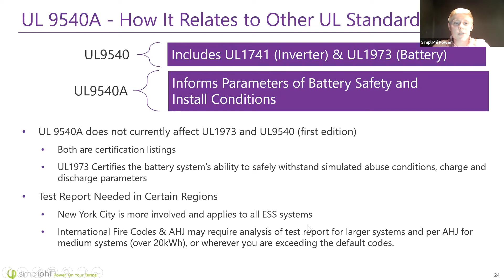What I want to highlight is that the test report is going to be needed in certain regions and for certain size systems. For example, New York City often requires a 9540A test report. Depending on your authority having jurisdiction, you might need this for larger and medium-sized systems as well, so make sure to check with them.